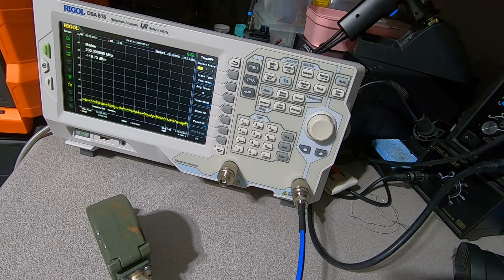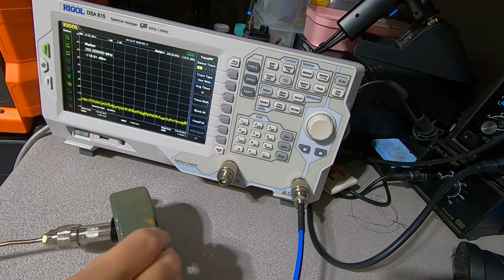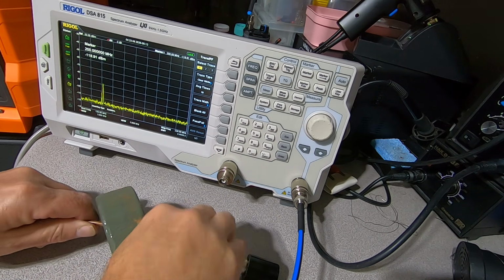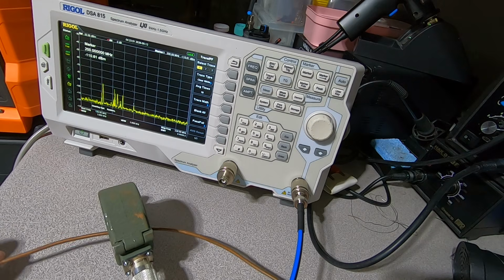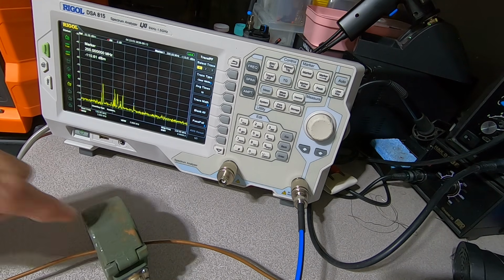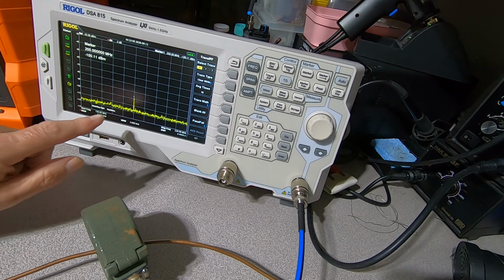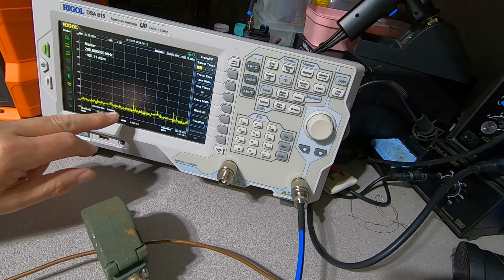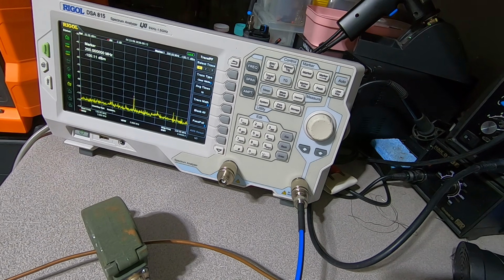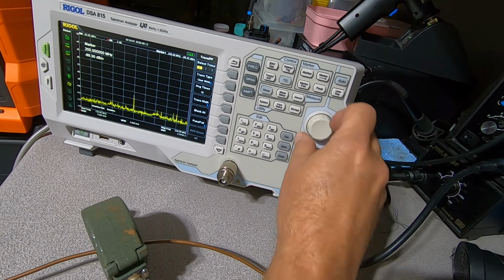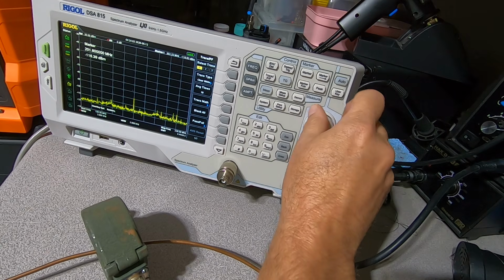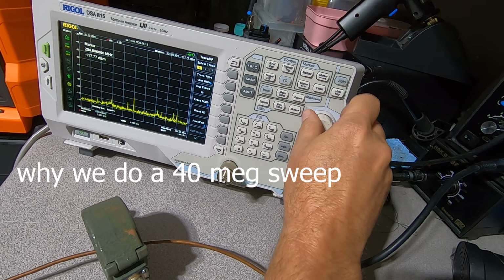Okay, let's go ahead and test a cable. We've got this section of RG402 here, a 50 ohm load, and now you see the big weakness with this kind of test, and that is, look at the noise here. And we have a nasty spike here at 200 megahertz, so we need to adjust, and that's the reason why we set the frequency difference. So let's go ahead and move this to 205 megahertz.